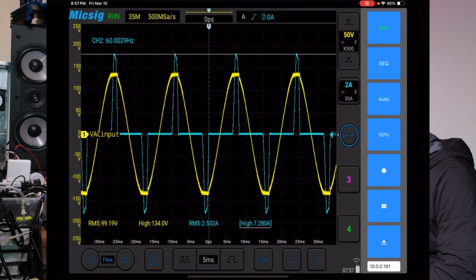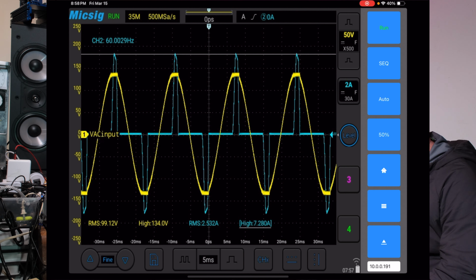All right, so now you're looking at the output of the transformer. It doesn't look a whole lot different, right? We're putting 90 volts RMS in, but now seeing 99 volts out, so it's a little more than a 1-to-1 turns ratio. The high voltage peak is 134, but look how flattened off the peak is. Why is it flattened? Because that peak current is a little less than at the input, since the voltage is a little higher, but it's flatter because where the current spikes up, it flattens off the voltage due to an IR drop. IR means current times resistance, Ohm's law. So we lose voltage across the winding of the transformer, which flattens the voltage peak when the current pulses on, giving a bit more distortion on the voltage.